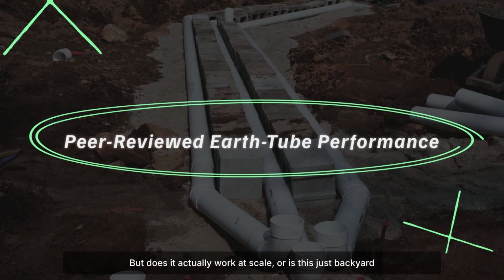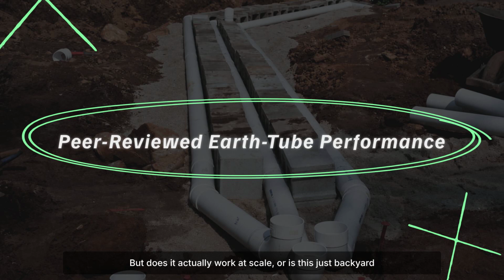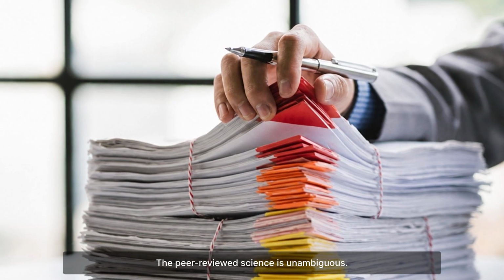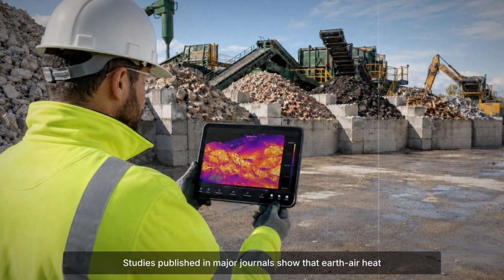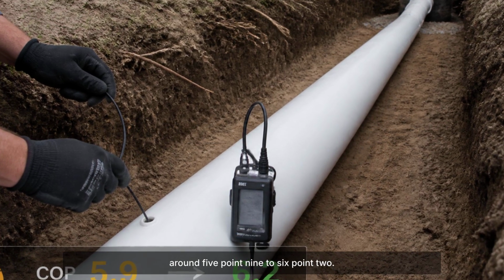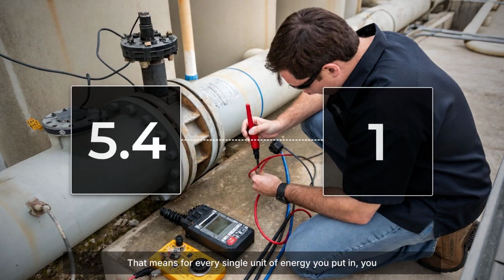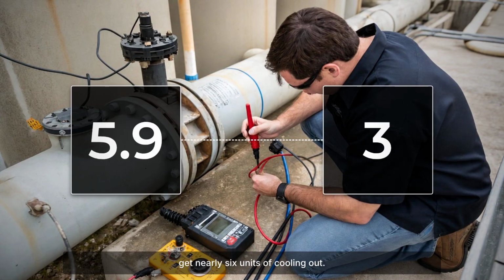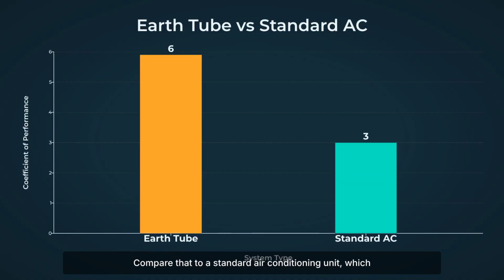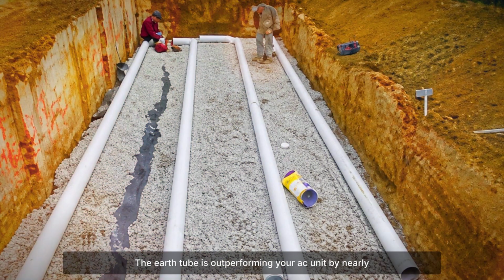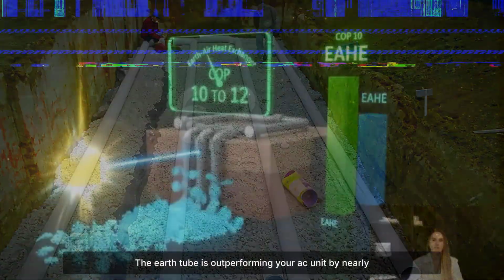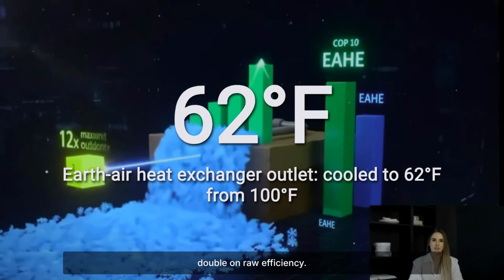But does it actually work at scale, or is this just backyard tinkering? The peer-reviewed science is unambiguous. Studies published in major journals show that earth-air heat exchangers deliver cooling coefficients of performance around 5.9 to 6.2. That means for every single unit of energy you put in, you get nearly 6 units of cooling out. Compare that to a standard air conditioning unit, which achieves a coefficient of performance of 2.5 to 3.5. The earth tube is outperforming your AC unit by nearly double on raw efficiency.